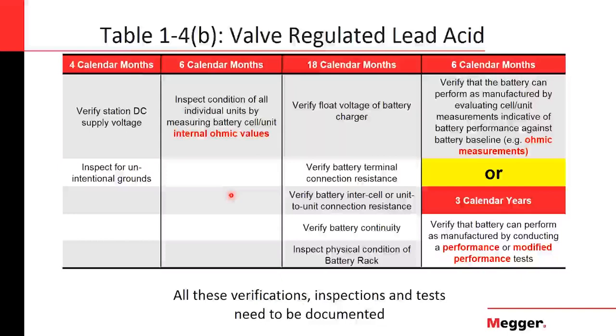In these batteries, you don't have clear jars. Usually they are, depending on the manufacturer, gray or orange, so you won't be able to see through the battery. The electrolyte is still lead acid, but it might be in a form different than a liquid, so you really cannot inspect the electrolyte level. That's why it's not in the 4 calendar months inspection. And because you can't see through the jar, you need to use another method to try to determine what is going on inside the battery. So that's why this table includes the 6 calendar months, asking for internal ohmic values. This is a requirement to perform every 6 calendar months on these batteries.